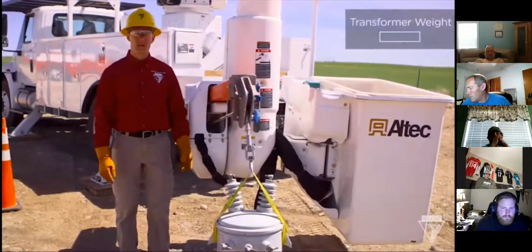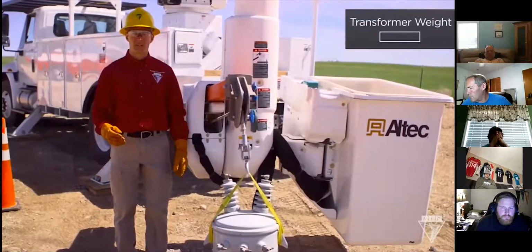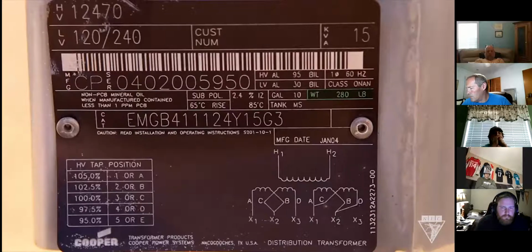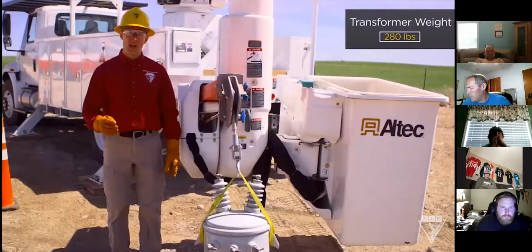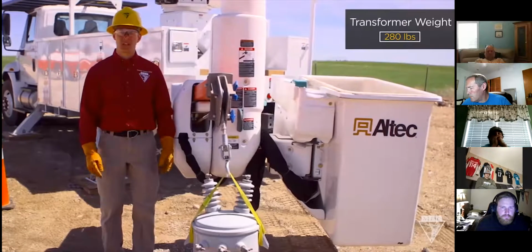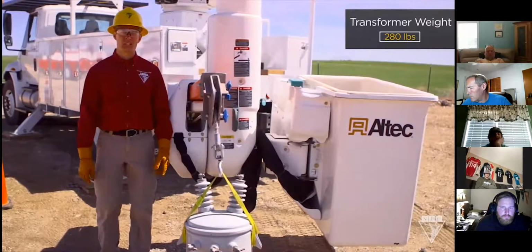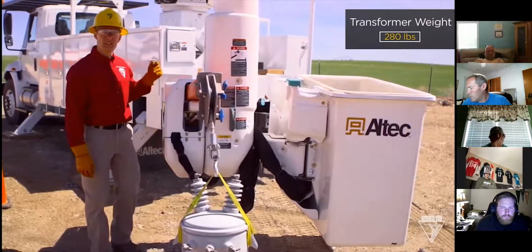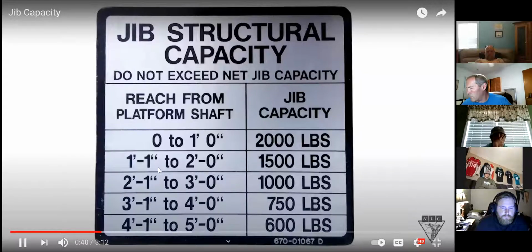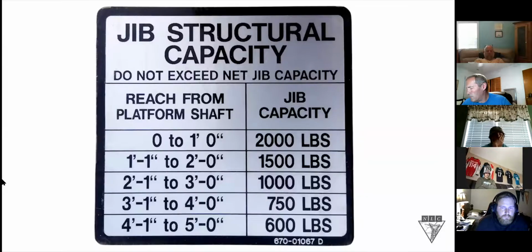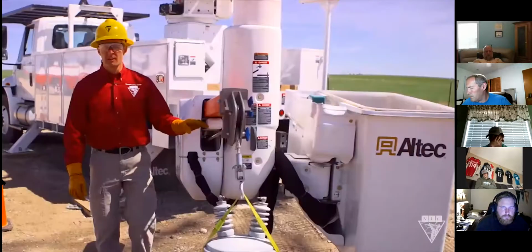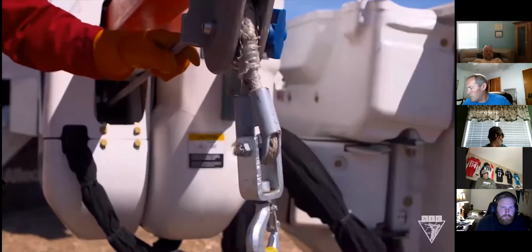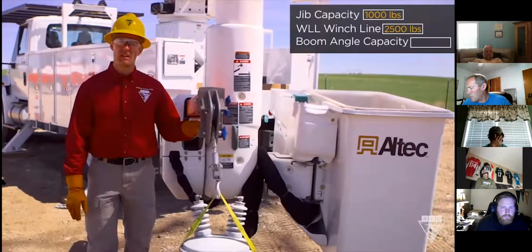So here I'm set up to lift this transformer. I looked at the nameplate, so I know it weighs 280 pounds. Now I have to make sure I can pick it up safely. This Altec truck has a jib capacity placard on the top side of the jib. Here I can find the max weight that can be lifted at different extensions. To install this transformer, I know I'll need to extend it about 2.5 feet, which puts me at a limit of 1,000 pounds. This winch line has a working load limit of 2,500 pounds, so I know I'm safe here.